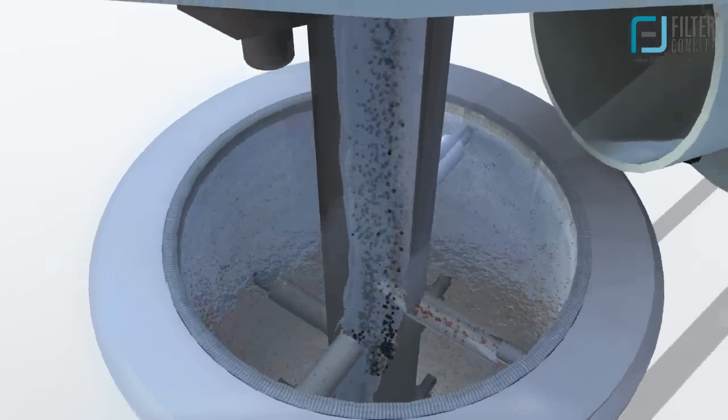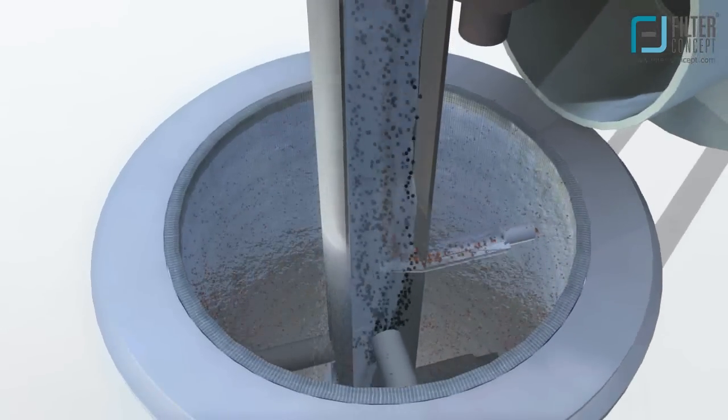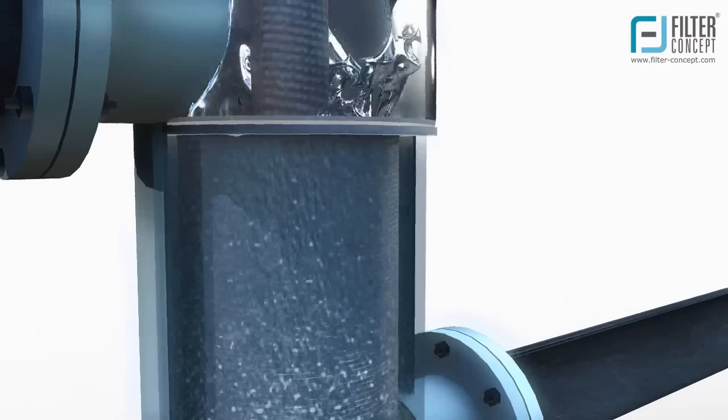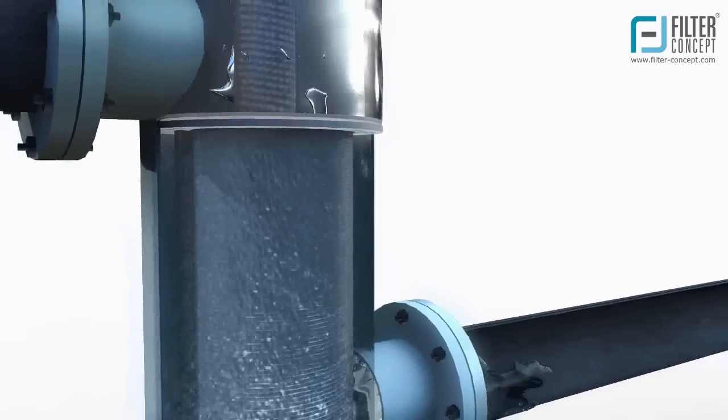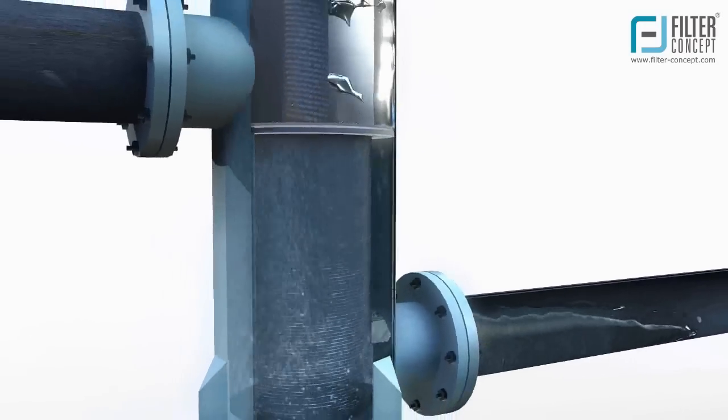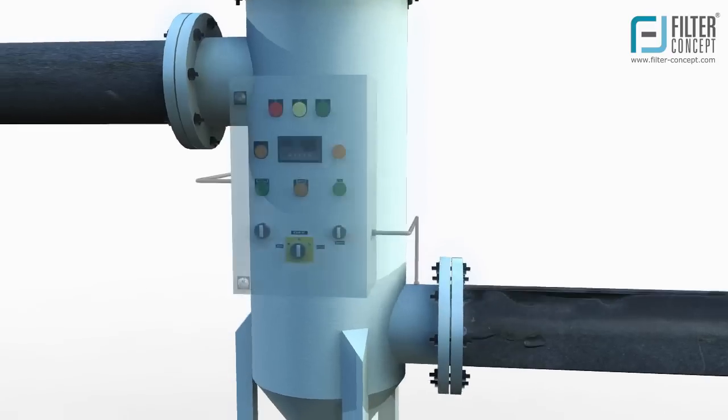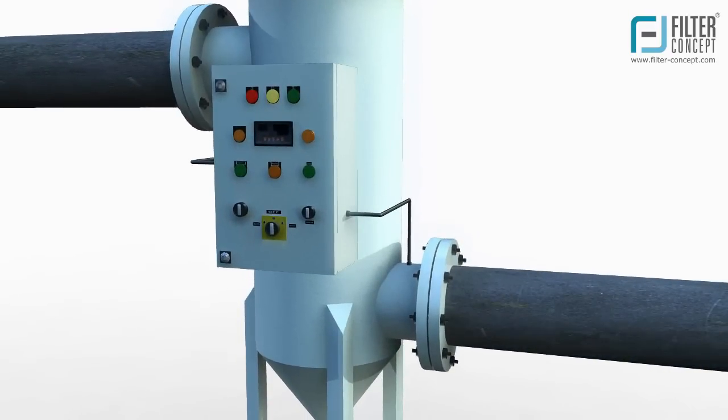Dust extraction assembly is also connected with back flush valve, that has freely open end to the atmosphere. The most important part about auto back flush self-cleaning is, while system is in cleaning mode, the system is in working condition without interrupting its filtering process.